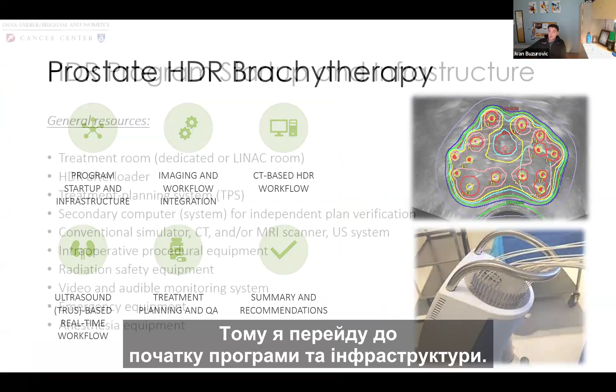So I will skip to the program startup and infrastructure. Unfortunately, I cannot talk in depth, but here I will outline all the equipment that is required to start or to expand the HDR program. It is necessary to have a shielded treatment room, either dedicated or a Linac room. We have had both, and our experience with sharing a Linac room for brachytherapy was not too successful, but of course, we have to do what we have to do. It is necessary to have a device that is responsible for automated delivery of the dose, which is the HDR afterloader, a treatment planning system, and a secondary computer for independent plan verification.